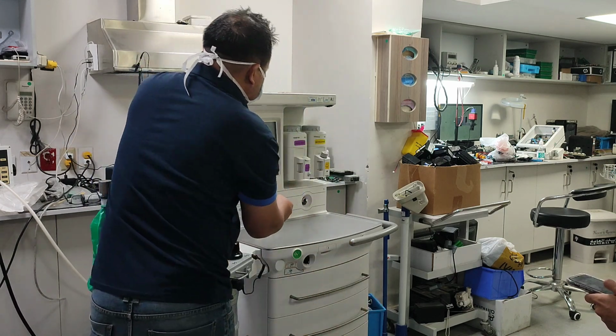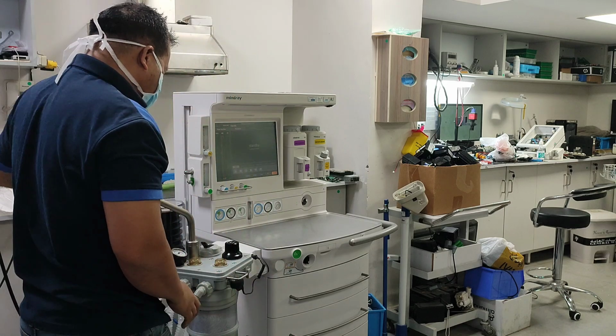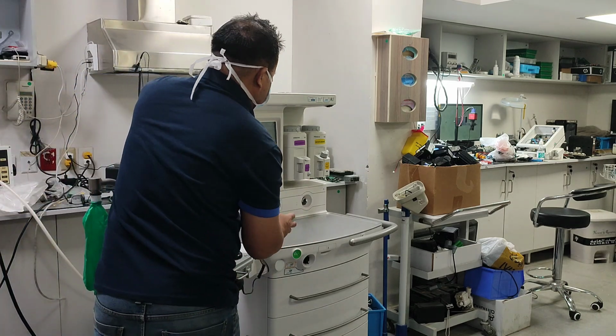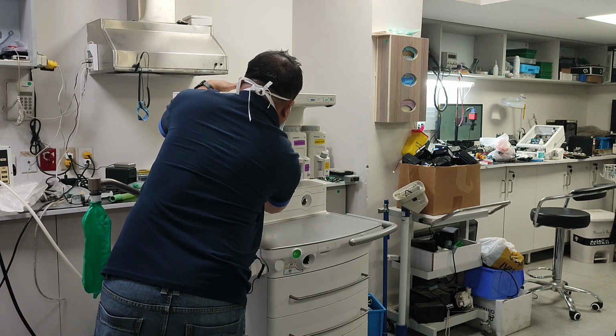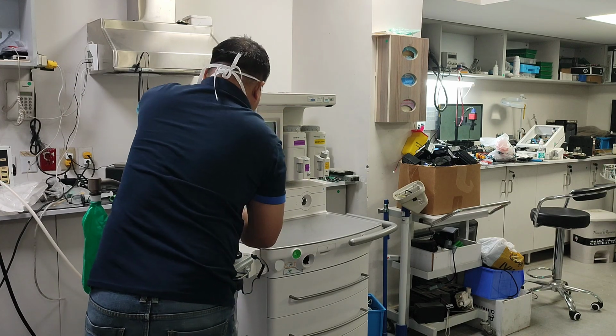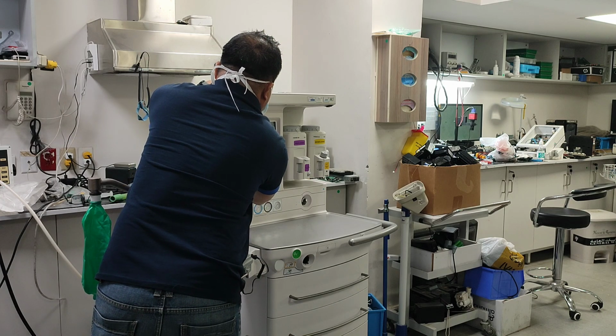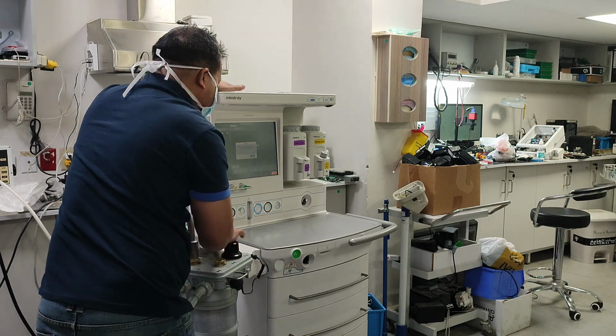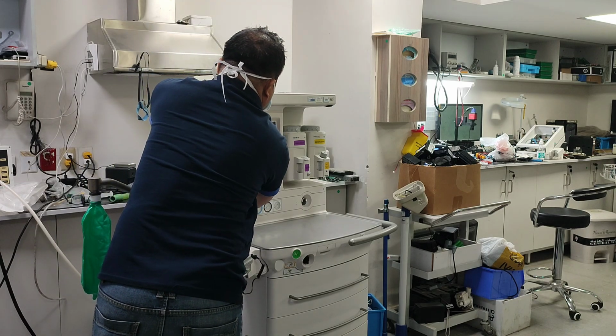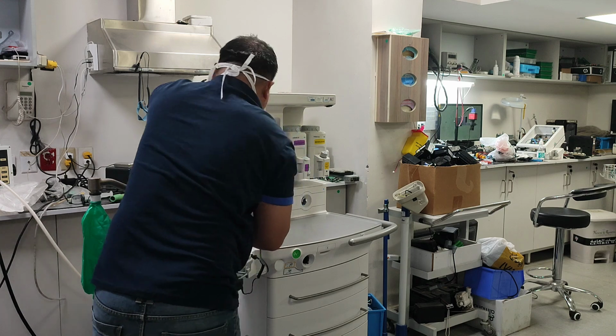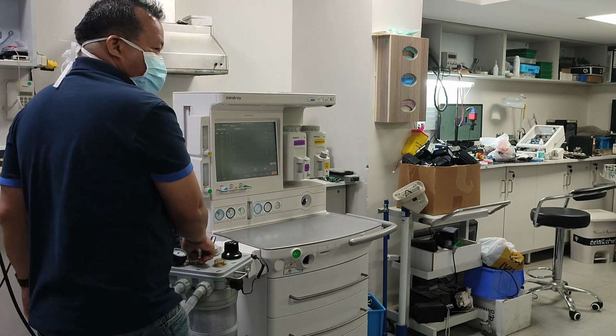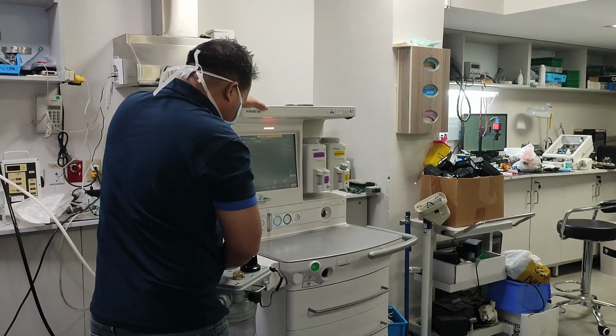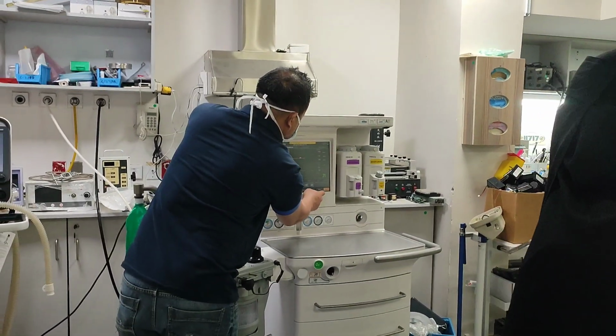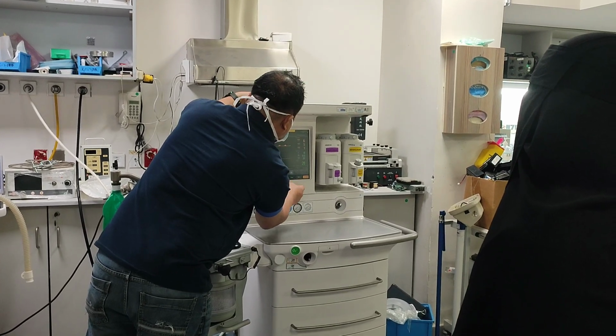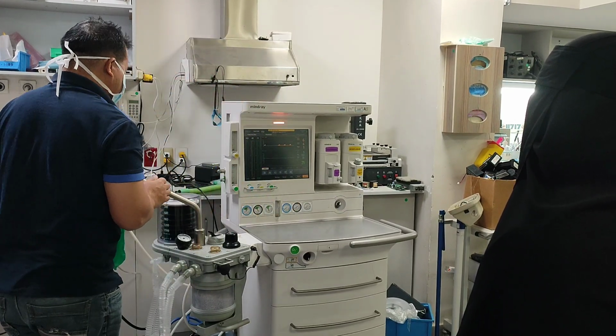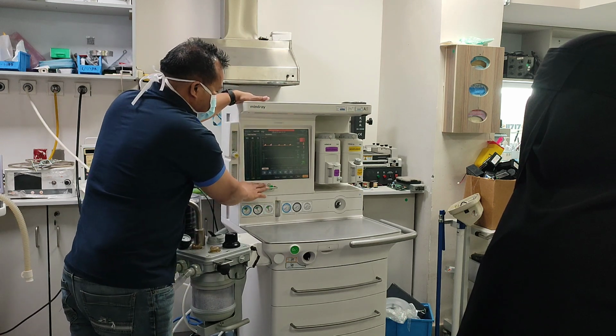So here it is the same as the ventilator. I will give you the basics of the parameters of this anesthesia machine. When you touch this screen, you put it in manual. It will not start this ventilation if it's in the automatic position. See, if I put it in automatic and then I start here, it will not start. It will give you an alarm. Why? No pressure gas. Okay, there's no pressure gas because we need to open this one.